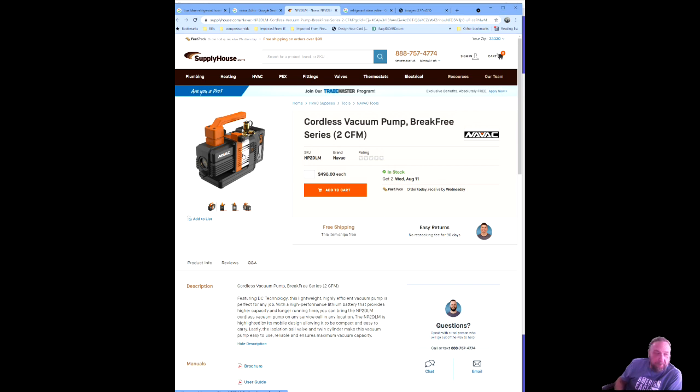I've pulled vacuums with a vacuum pump and reached 20 microns within less than 2 or 3 minutes. You know what I mean? Back in the days when we were doing refrigeration systems in the 80s, we didn't have micron gauges. So we always thought, let it run 20 minutes or 25 minutes and you're good to go. If it holds a vacuum, let's go. So again, at 2 CFM, that's how fast it's going to pull down, not how deep.